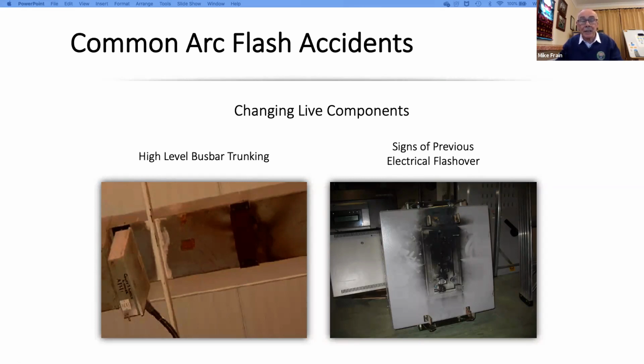And I was doing an audit there. And you can see, I was looking up at this 800 amp busbar trunking. I could see these burn marks where the tap-off point was. Trouble is, when I asked what they were, when I was doing the safety audit, I discovered that the current electrical manager didn't have any knowledge of it whatsoever. And they were actually doing exactly the same thing that led to the hospitalisation of an electrician some years earlier. I finally got hold of one of the old hands, who told me all about what happened, and he was badly hurt by the sounds of it.